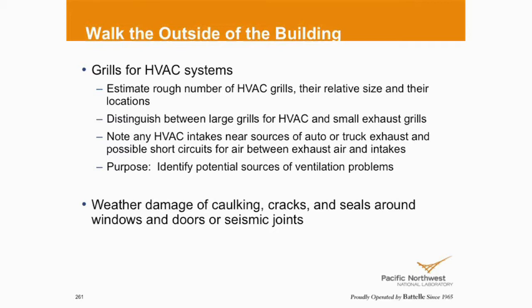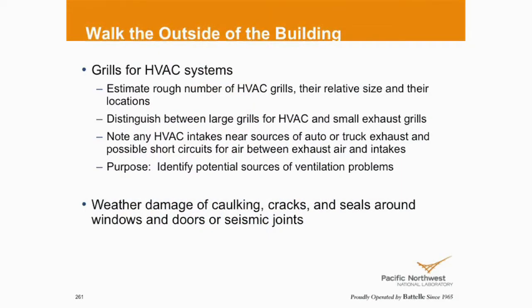HVAC grills, when you're walking the building down, again, intakes, exhausts, are they near each other? Do we have exhaust points near loading docks? We see that a lot. And because of VFD-driven supply and return fans, how many of you know this, that your exhaust point can actually become an intake point if you're not operating your return fan properly? It can. If I slow my return fan down to the point that my supply fan overpowers my return fan, it will start sucking in through the outdoor intake and the exhaust, what should be the exhaust point. And if that exhaust point is near a loading dock, and we found that, believe it or not, at another college. So again, indoor air quality issues potentially.